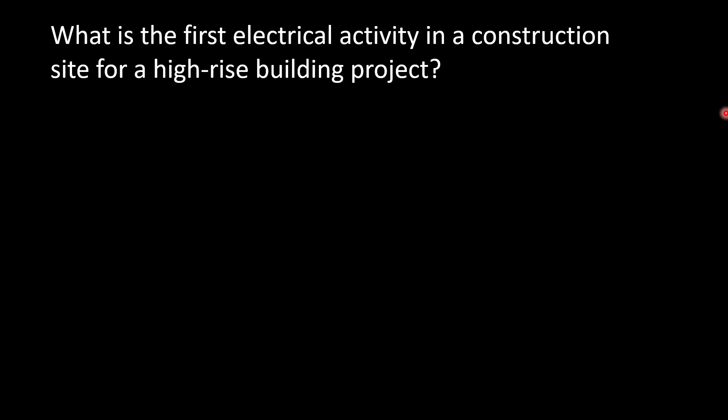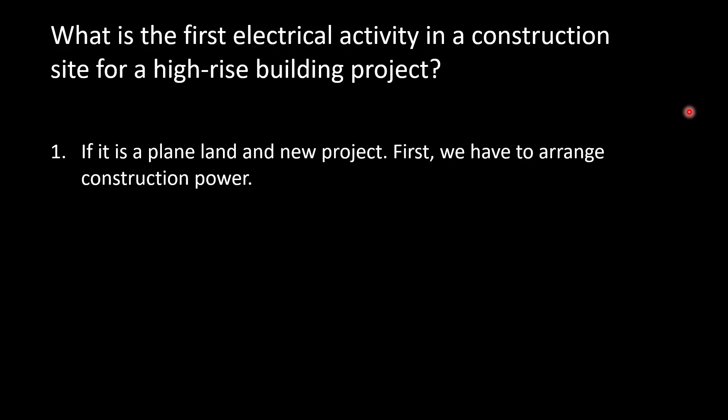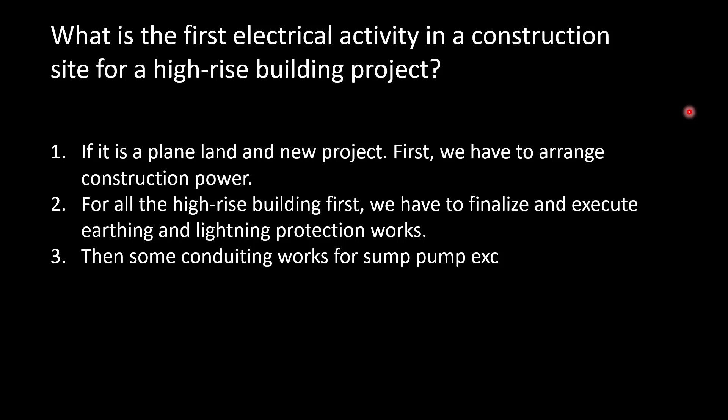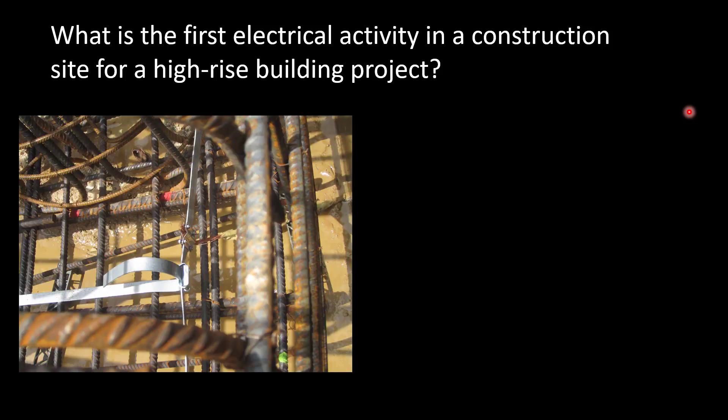The next question is: what is the first electrical activity on a construction site for a high-rise building project? If it is an entirely new project starting from scratch, the first activity will be arranging construction power for construction activities — also called temporary power. We have to arrange temporary power and a site office. For a high-rise building project, the next activity will be lightning and earthing works. We have to finalize lightning and earthing protection materials. The first activity shall be lightning protection works, because it is normally done below the plinth or below the raft. Parallel to this, some conduiting works in small columns and walls will also begin. This is a sample picture of a lightning protection earth mat or foundation earthing on the raft or plinth.